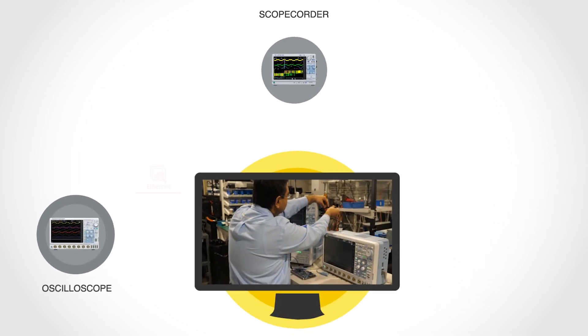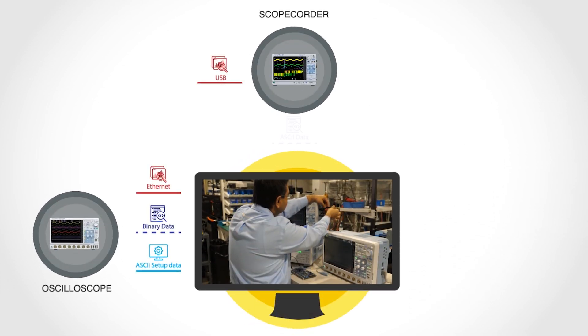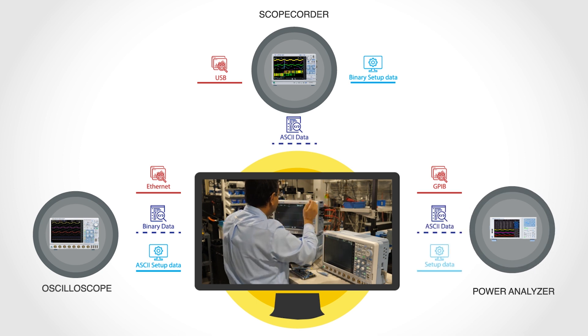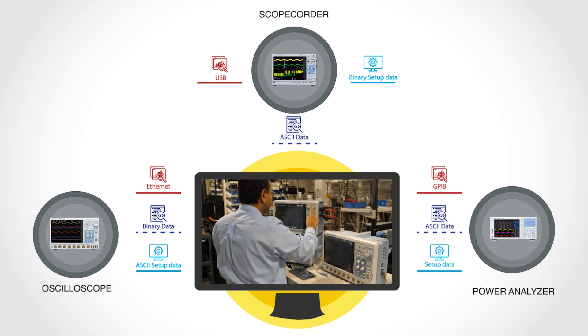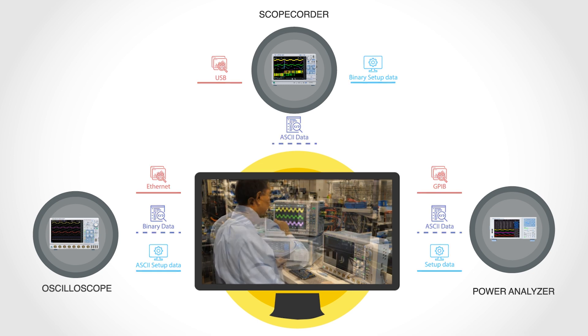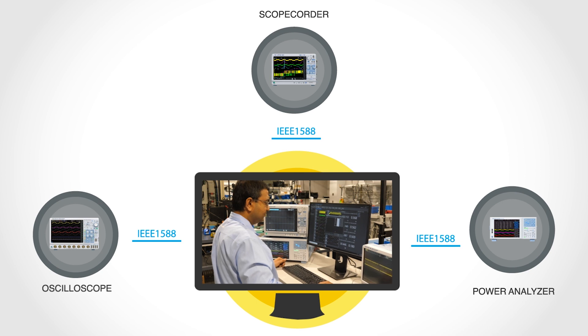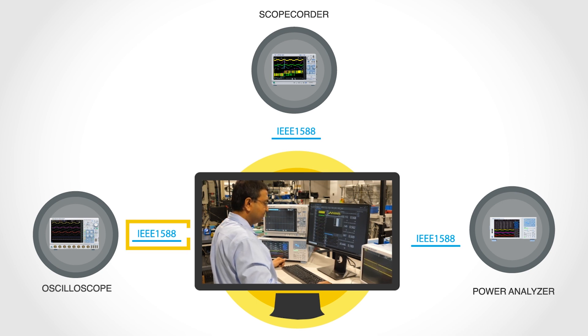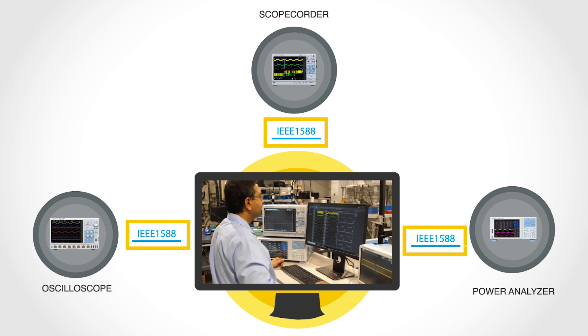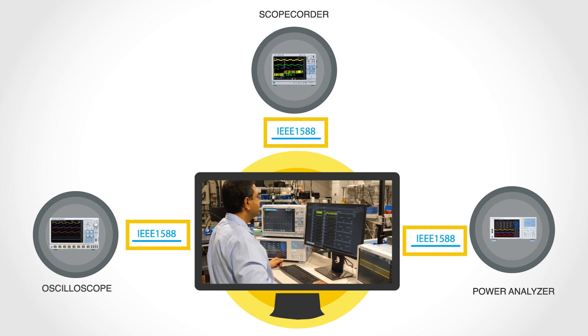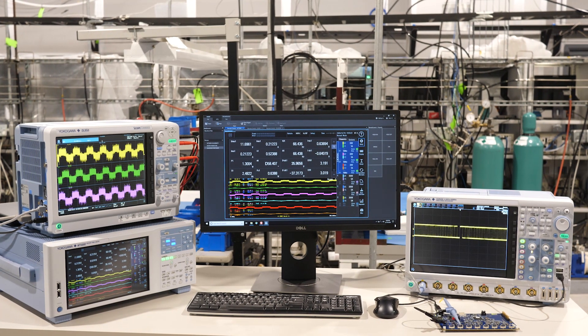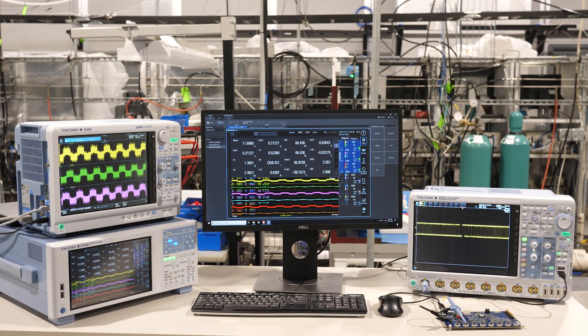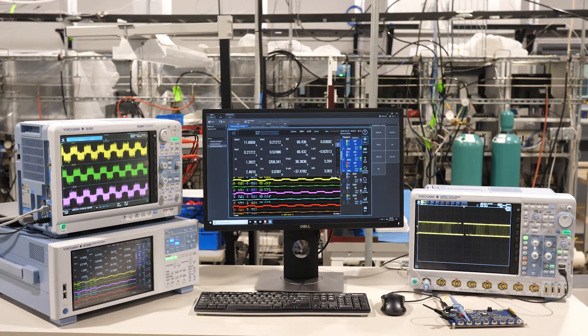Collecting, analyzing, and maintaining large amounts of test data from multiple instruments, each with different formats and different storage locations, can be a daunting task. Each instrument has its own device drivers with unique communication interfaces and synchronization protocols for clock and data. Using the IEEE 1588 precise time-based protocol, the IS8000 provides synchronized and accurate measurements across multiple instruments, with one format and one storage location. The ability to view all measurements on a common display provides engineers confidence and trust.